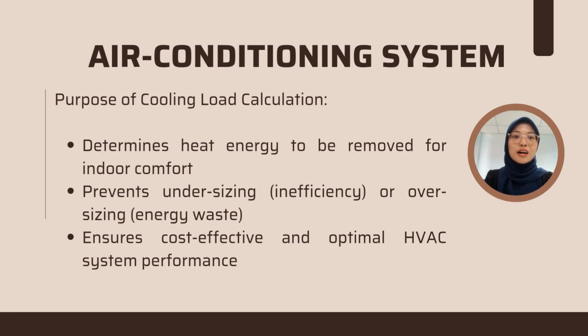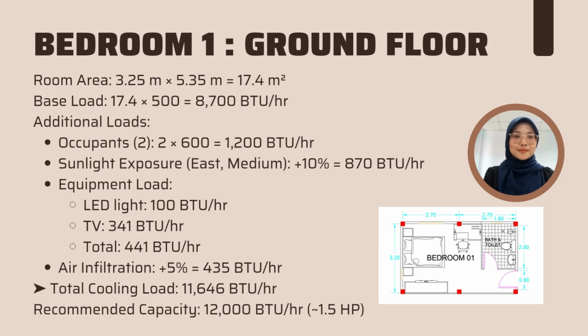Now, I will explain the cooling load estimation process for selected room in this project. Cooling load refers to the amount of heat energy that must be removed to maintain a comfortable indoor temperature. This step is essential to ensure that the air conditioning units are properly sized, not too small, which will lead to inefficient cooling, and not too large, which will waste energy and increase costs. This cooling load calculation considers the room area, number of occupants, sunlight exposure, equipment usage, and air infiltration.